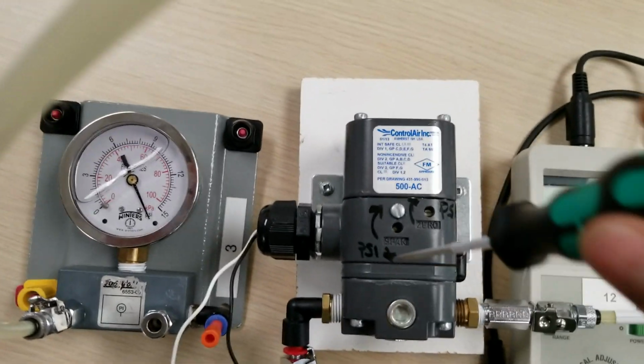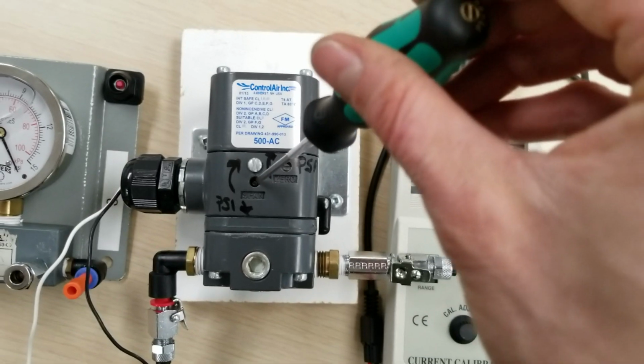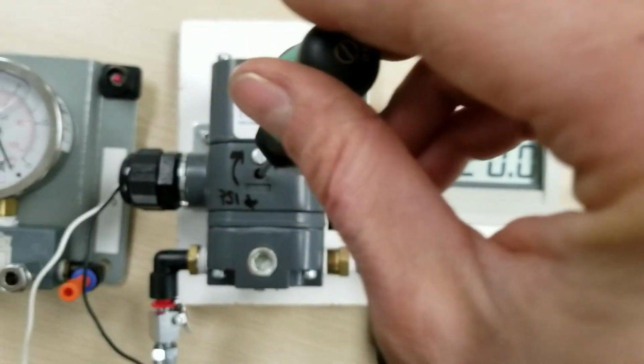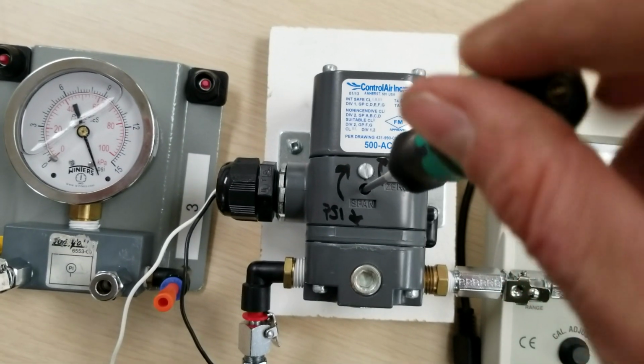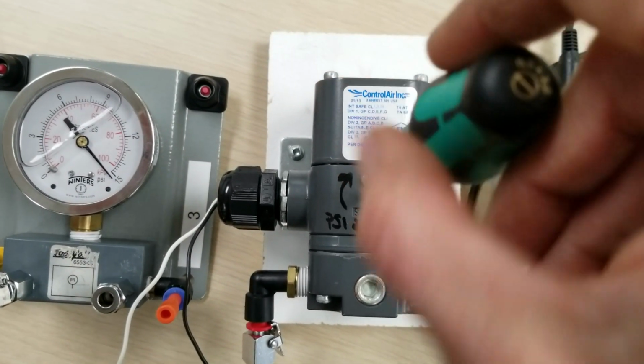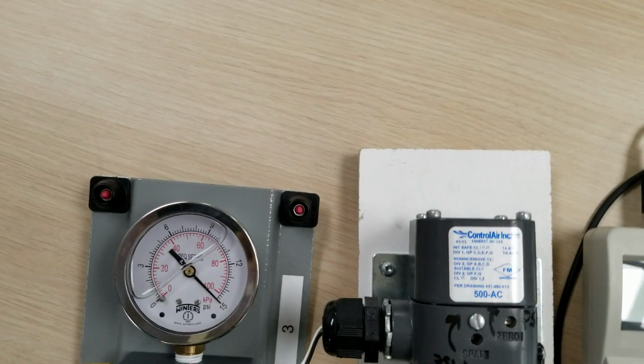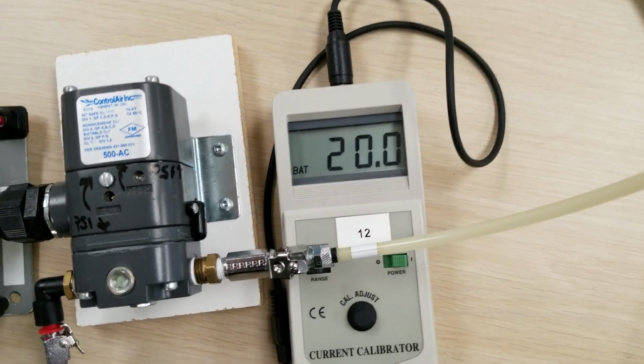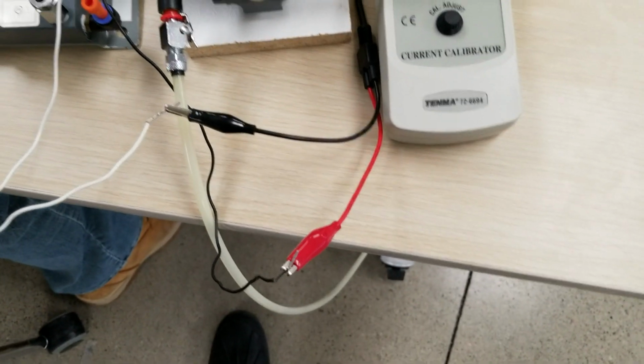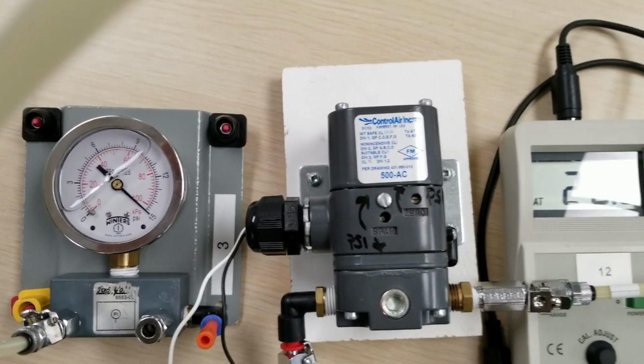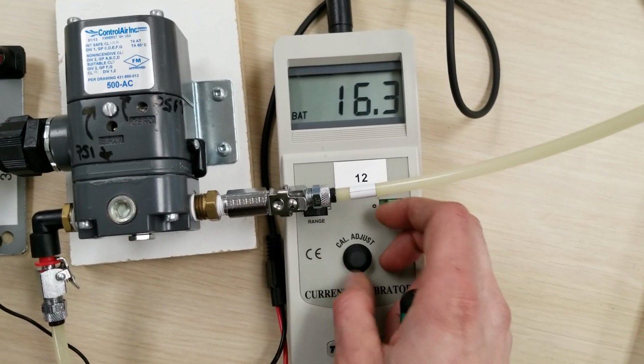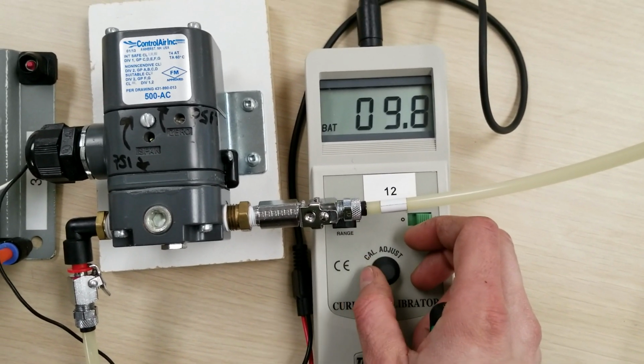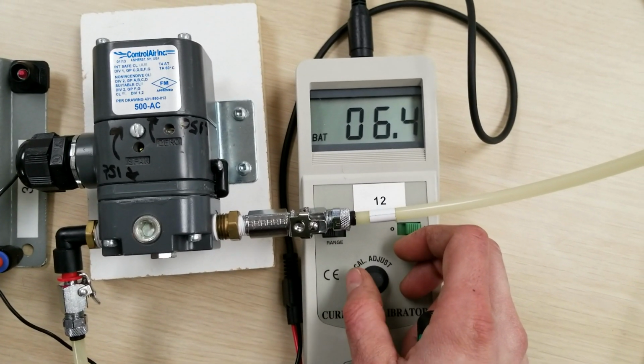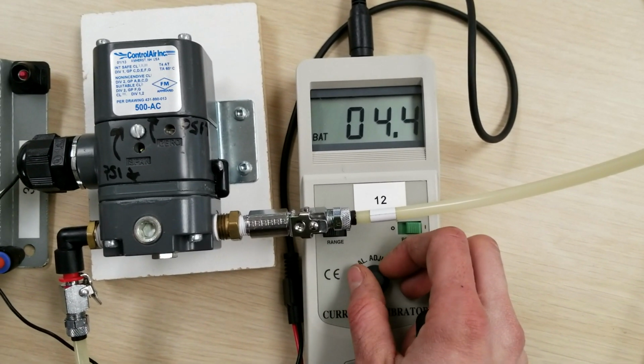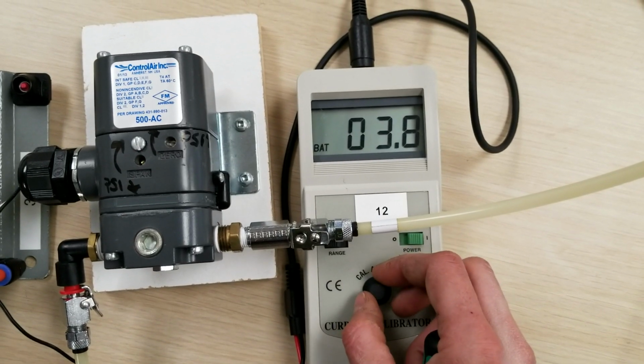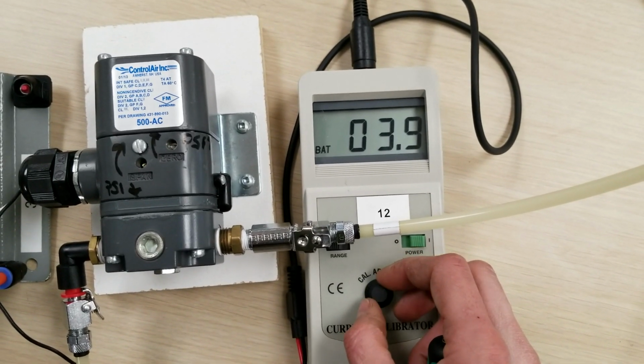And I will now adjust my span so that I have 15 psi on my 20 milliamp signal. Now I'll double check to confirm that I don't need to adjust my zero again. Let's make sure we have accuracy. We are doing some calibration so that we have accuracy.